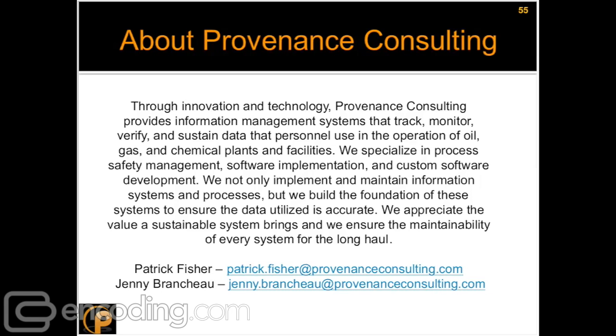Okay, thank you. How do you identify the PFD of individual components? Well, sometimes if it comes down to the level of, for example, an input-output block, you can get that information from the manufacturer. But going back to, I think, one of the very first questions here, which was around adding up the PFDs versus just using the lowest, we use a lot of approximations, and to determine the PFD of the component, you can get industry data or look to the purple and blue books. They have some examples. So the example I gave in the presentation was where a relief valve depends on a check valve. Both of those have PFDs defined in those two books. When it comes down to CPUs and I/O cards, go to the manufacturer, but those are probably going to be common throughout your facility, so you shouldn't have too much work there.